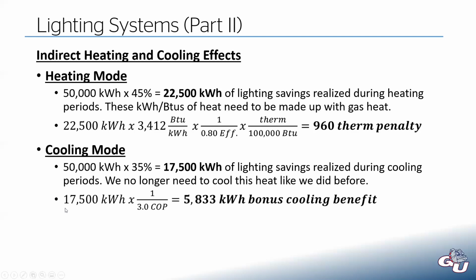If we no longer have to cool 17,500 kilowatt hours of heat, we have an air conditioner with a process that is 3.0 COP efficient. If you divide that by the COP, you arrive at 5,833 kilowatt hour bonus cooling benefit. So before the project, that's what the air conditioner had to spend to cool this heat energy that we've now removed. And so that brings us to the net savings.